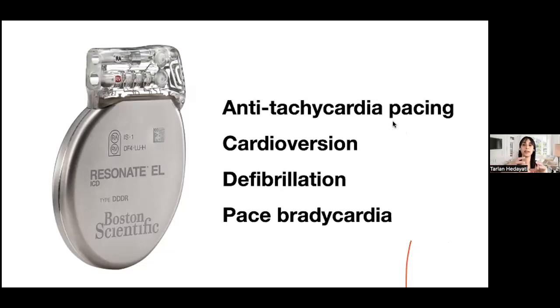They basically take the patient's heart rate, whatever it's running at, say VTAC running at 200, and ramp up the rate to, say, 210 or 220—typically 10 to 20 beats per minute higher than what the patient is running. Then they drag that heart rate down to a normal rhythm and normal rate. That's a low energy phenomenon, so the ICD doesn't have to exert a lot of energy to do that.